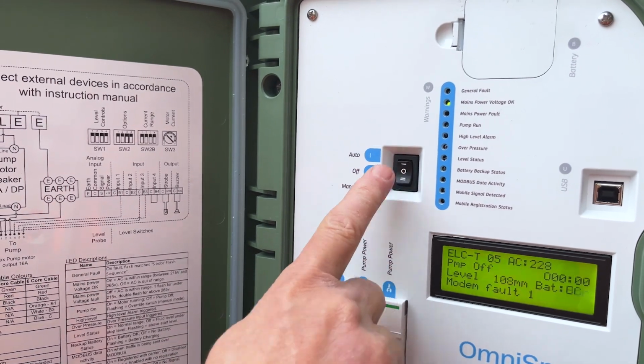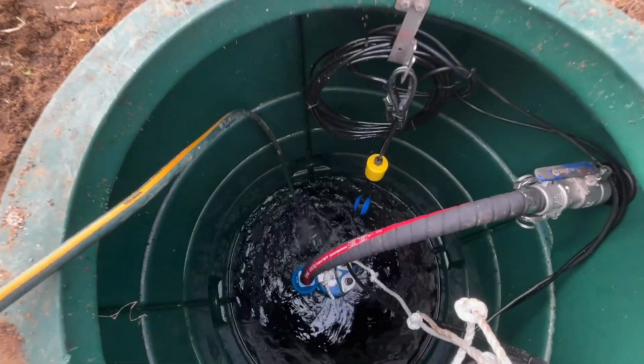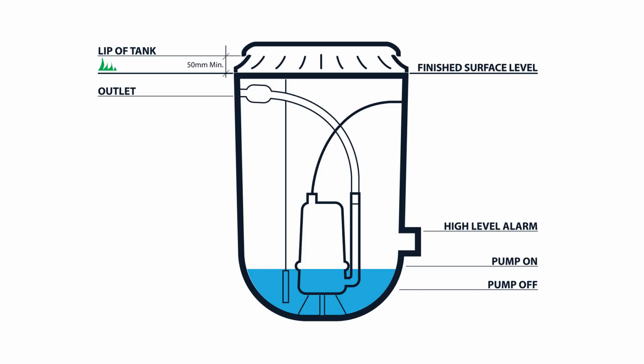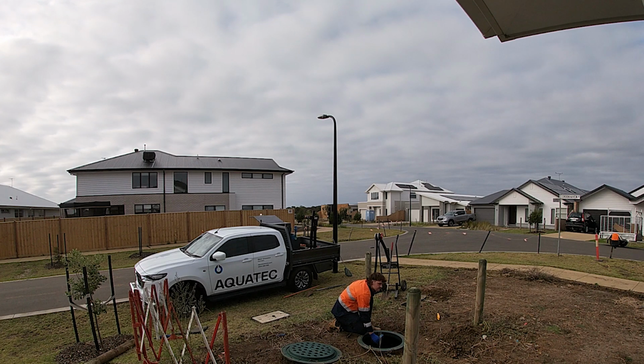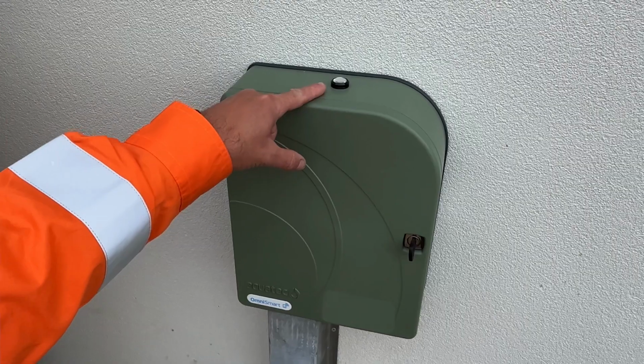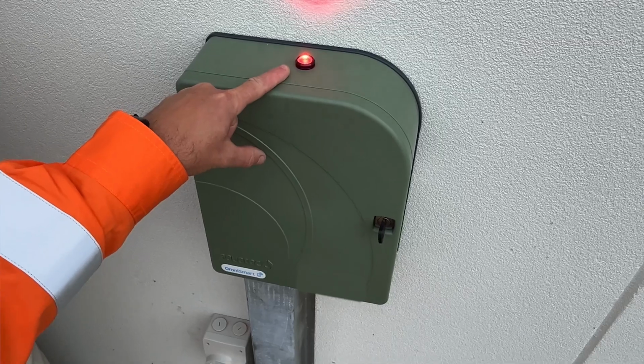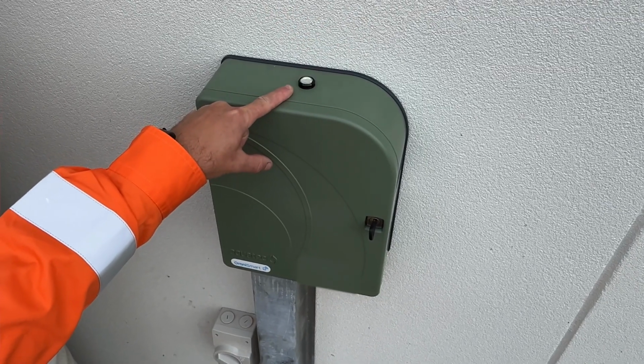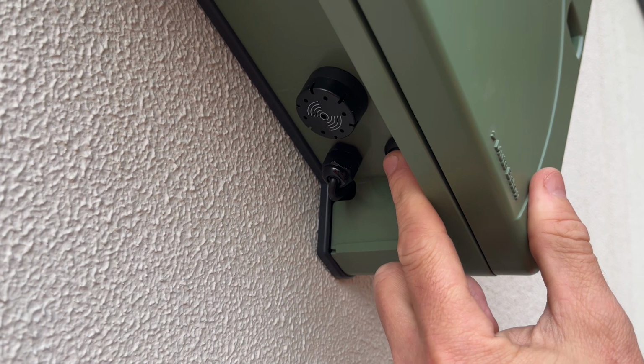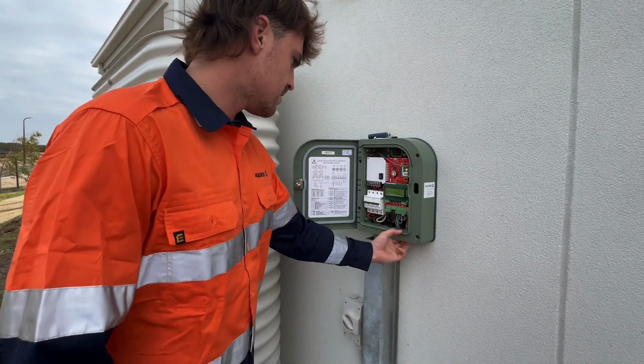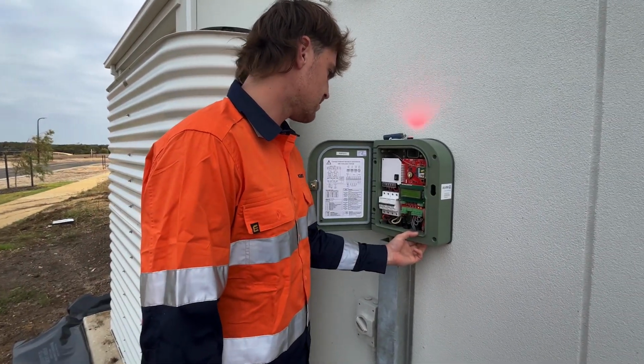Once that's been verified, turn the pump off via the selector switch whilst the test water is still running. And now with the pump off, the well continues to fill until we get to the alarm level point. Now we can verify that the visual alarm is working and the light is flashing. Now press the mute button to verify it actually mutes the alarm. This will mute the audible alarm, while the visual alarm will continue to flash until resolved.